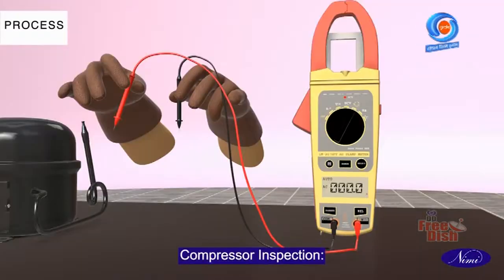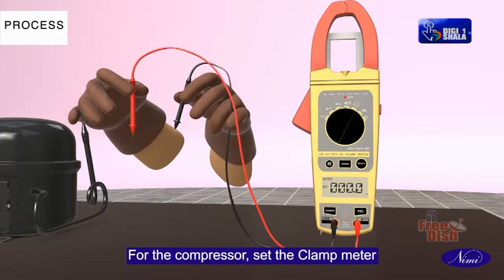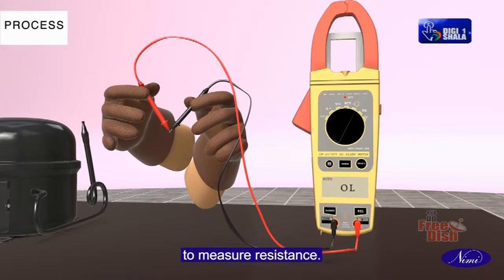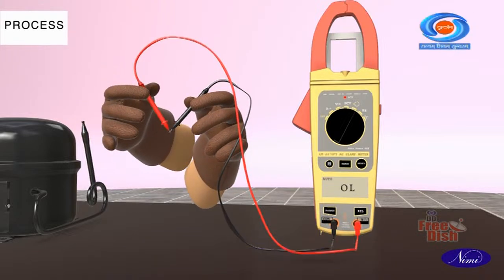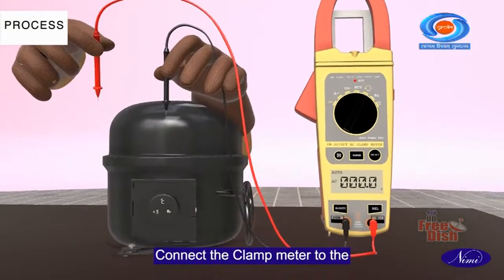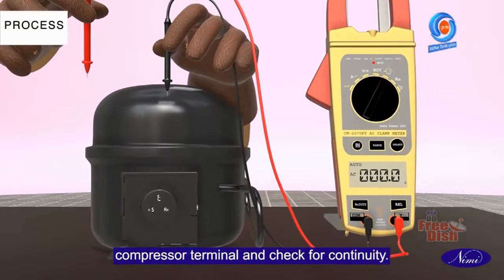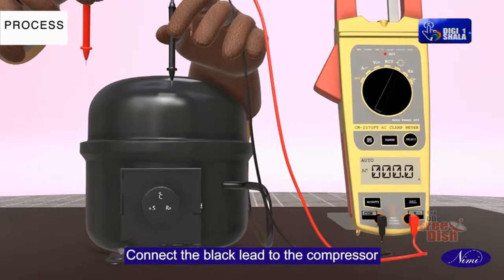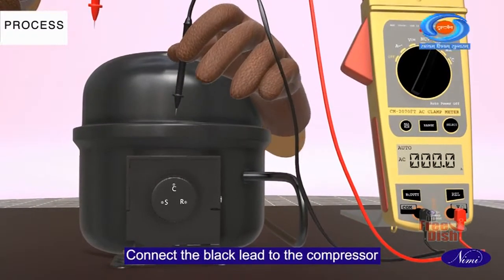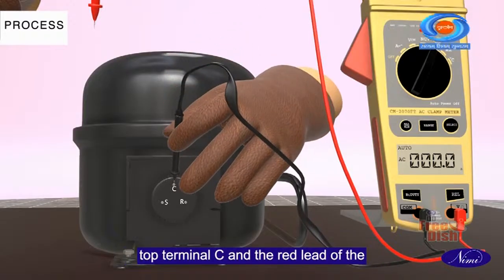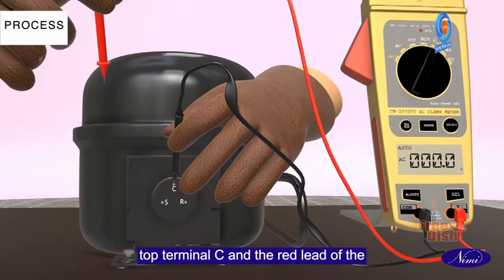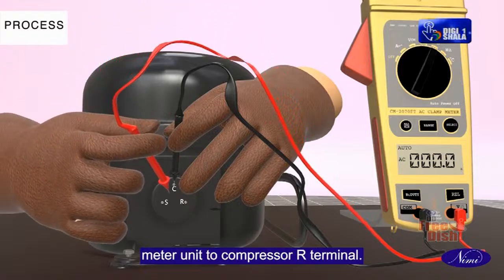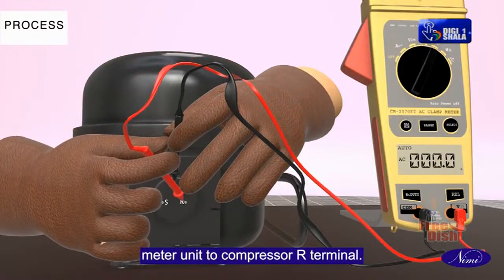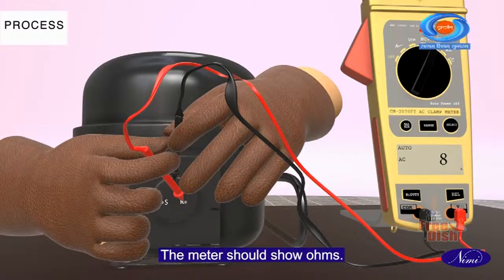Compressor inspection. For the compressor, set the clamp meter to measure resistance. Connect the clamp meter to the compressor terminal and check for continuity. Connect the black lead to the compressor top terminal C and the red lead of the meter unit to the compressor R terminal. The meter should show ohms.